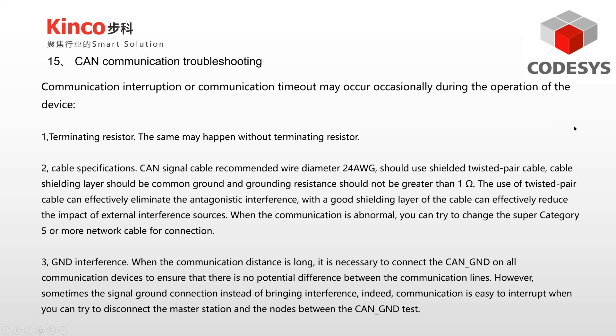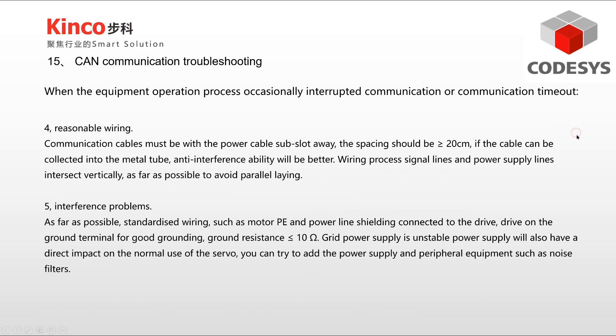However, sometimes the signal ground connection can introduce interference instead, causing communication interruptions. You can try disconnecting the GND between the master station and nodes to test. Reasonable wiring is also important: communication cables must be routed in separate conduits away from power cables. The spacing should be greater than or equal to 20 centimeters. If the cable can be enclosed in a metal tube, anti-interference ability will be better. Signal lines and power supply lines should intersect vertically and avoid parallel laying as much as possible.